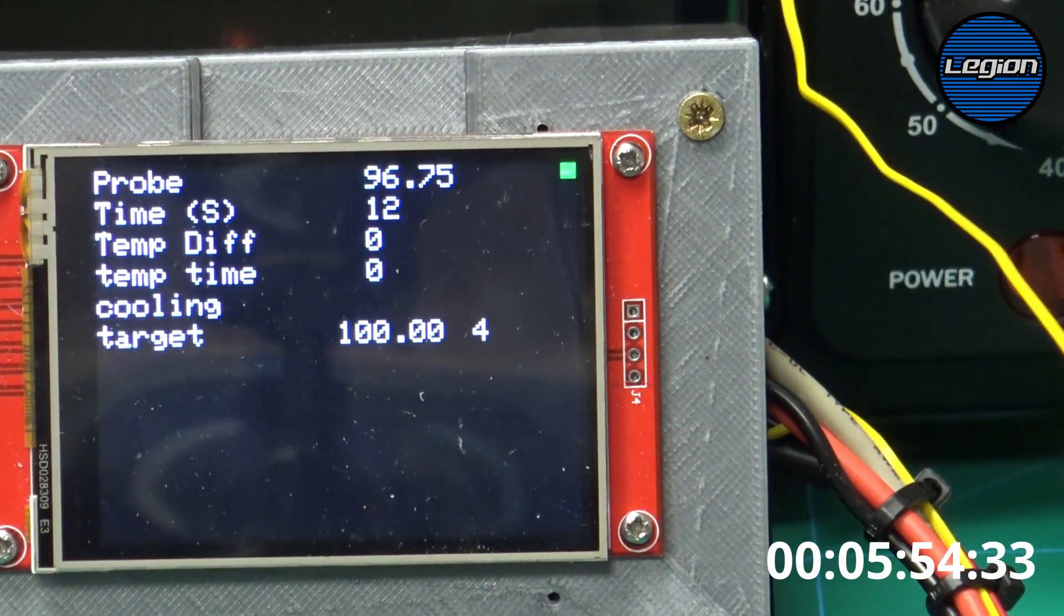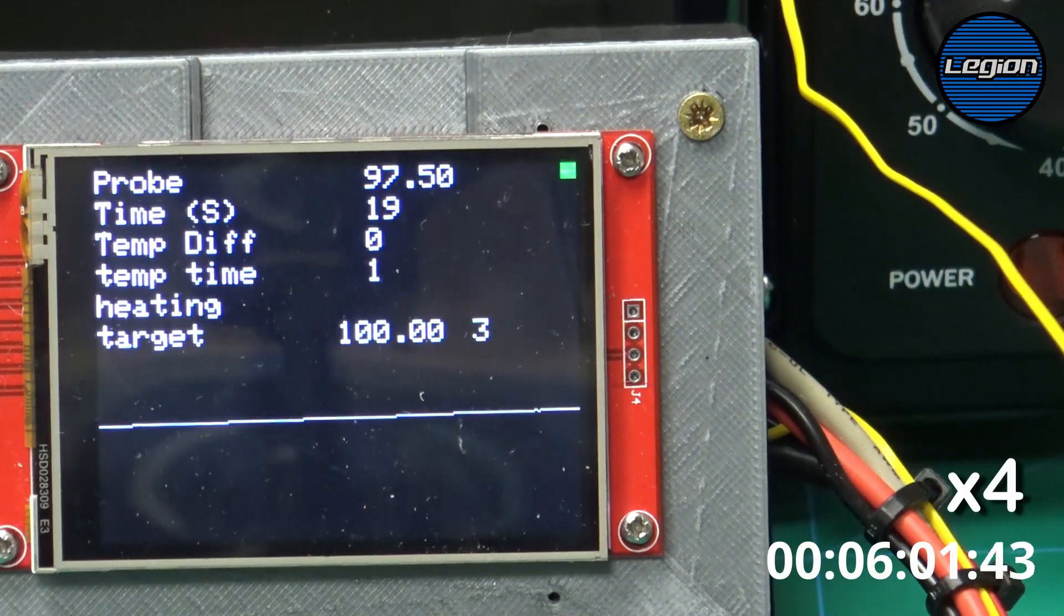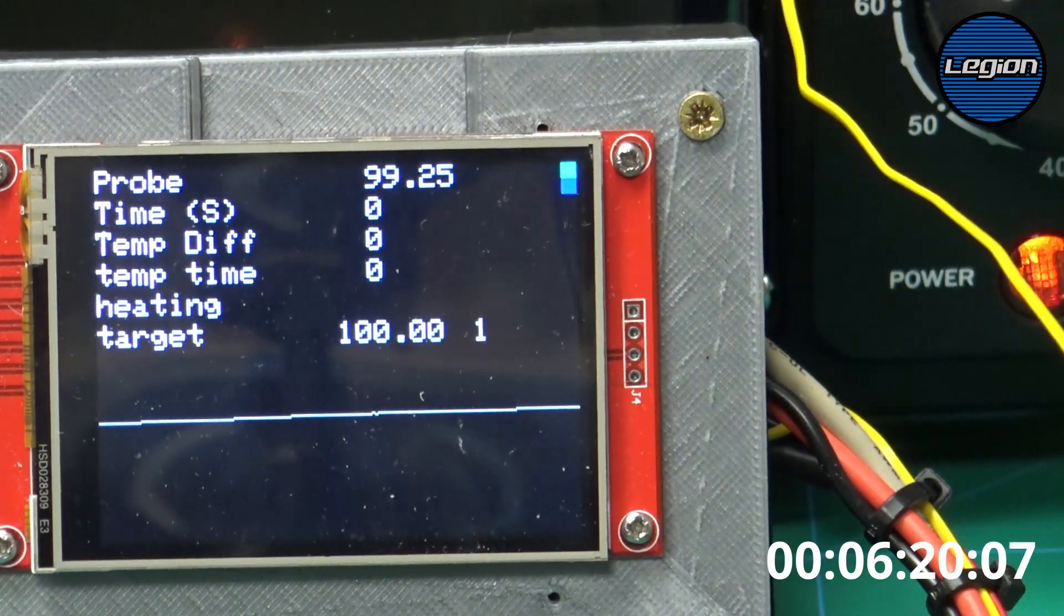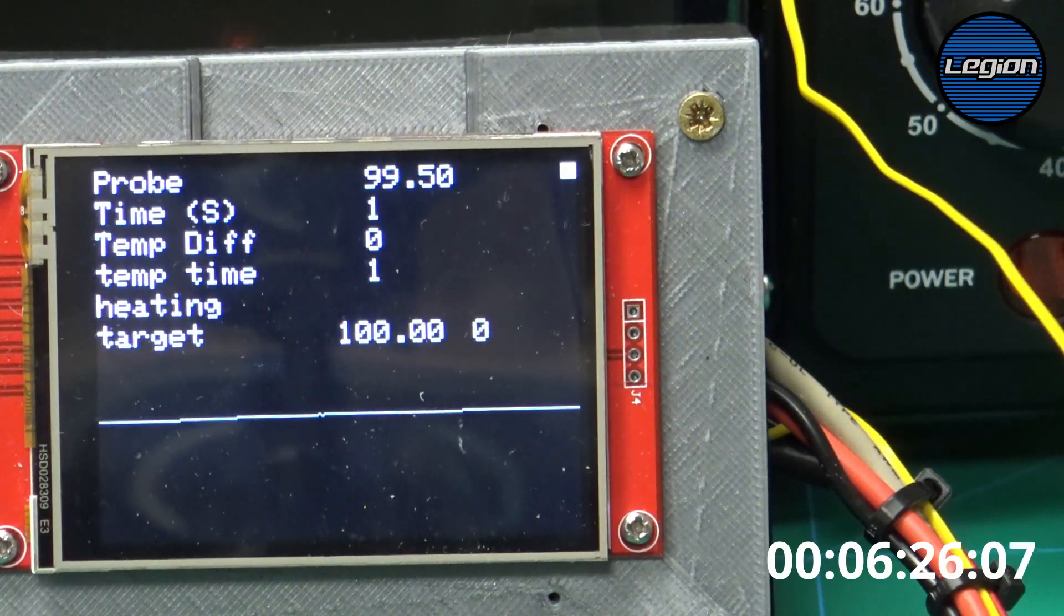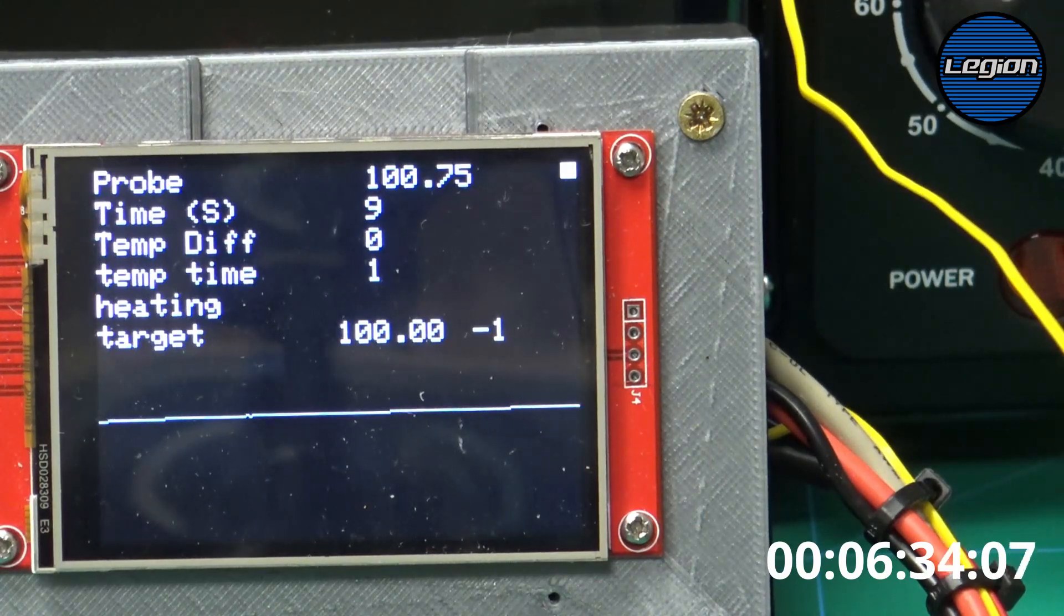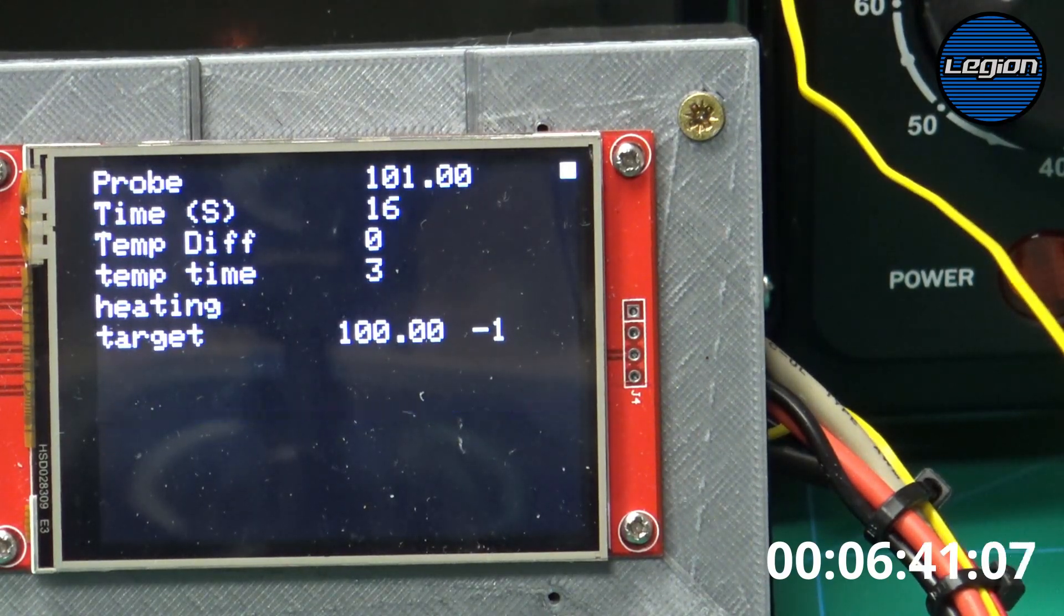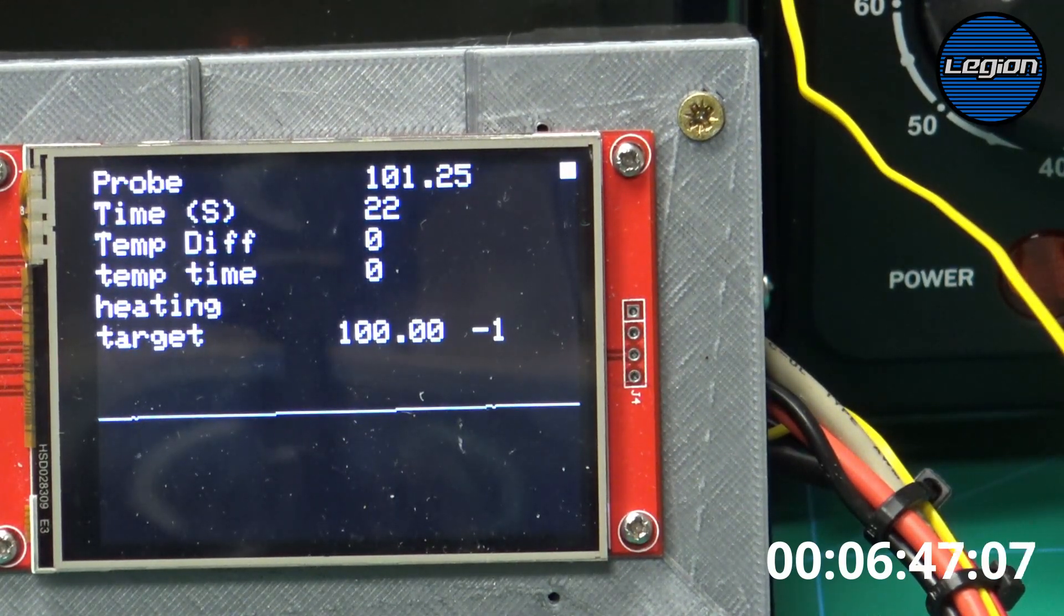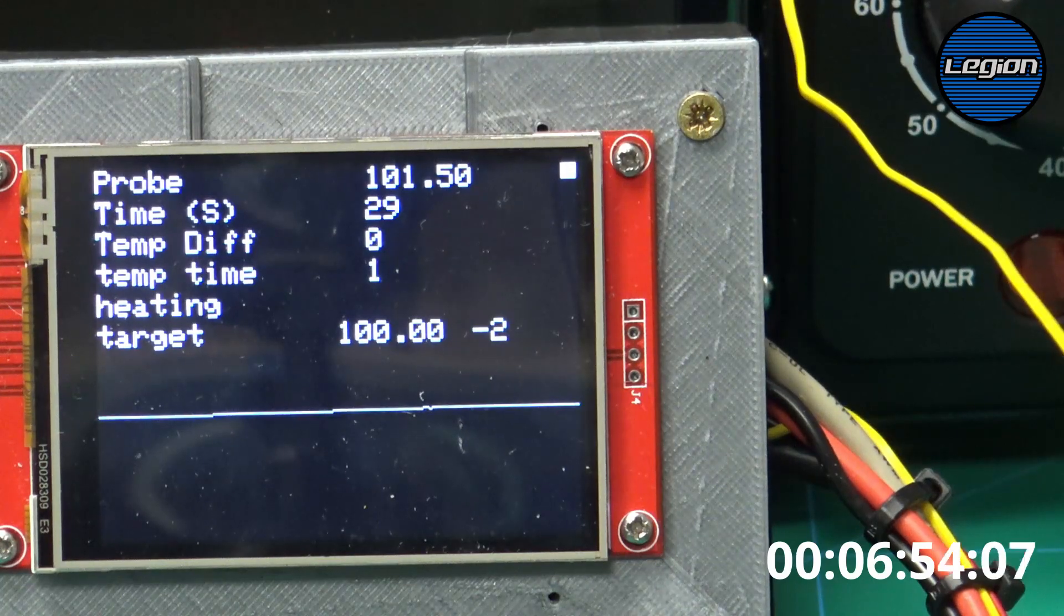We're now into the green range. I think this one is also 3 seconds but the heating element stays on for a little bit less. Now we're in the 1% range. And we've managed to get to our target without shooting over like we did before. We were going over by 10 degrees. So now that we're over target it will stay off. And then when it goes back down to 1%, it's programmed to see if the temperature trend is cooling. And then it will quickly blip the element.